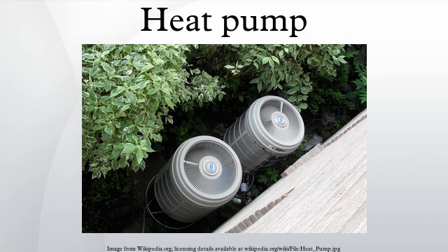Alternatively, thermal energy is transferred to water, which is then used to heat the building via radiators or underfloor heating. The heated water may also be used for domestic hot water consumption. The refrigerant is then allowed to expand, cool, and absorb heat to reheat to the outdoor temperature in the outside evaporator, and the cycle repeats. This is a standard refrigeration cycle, save that the cold side of the refrigerator is positioned so it is outdoors where the environment is colder.